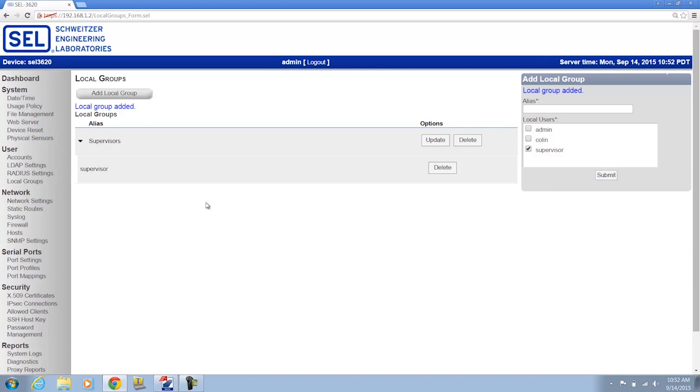Now when I'm doing local account authorizations I have to have matching groups both on the SEL 3620 interface as well as in Accelerator QuickSet. So that's what we'll do next.